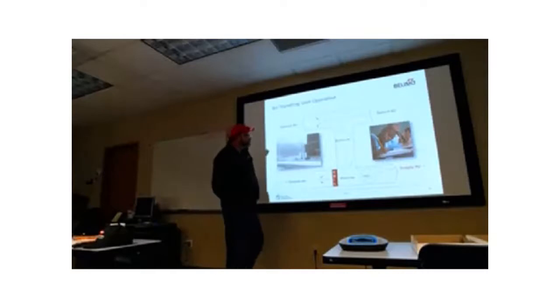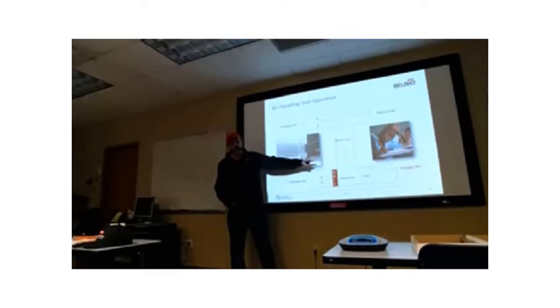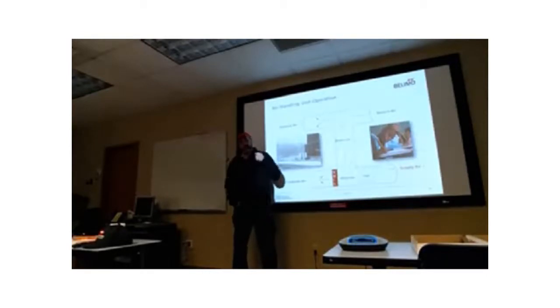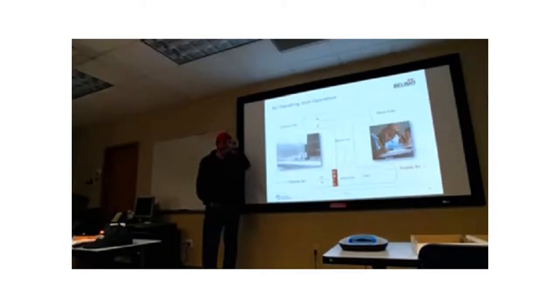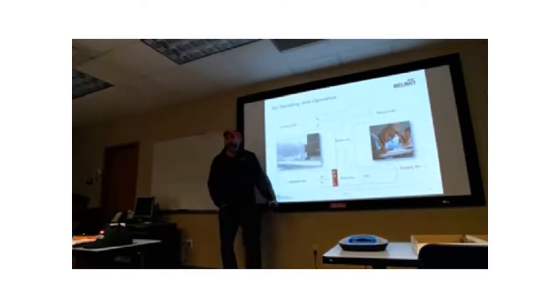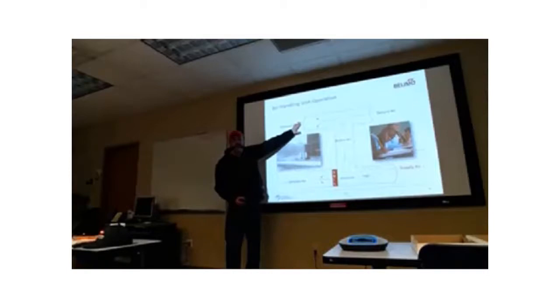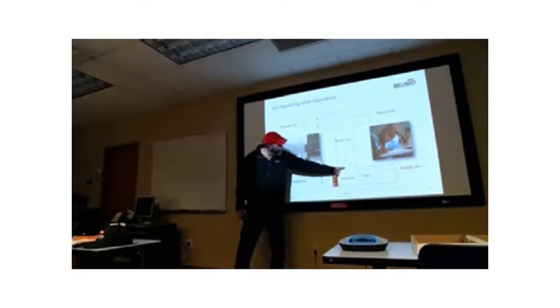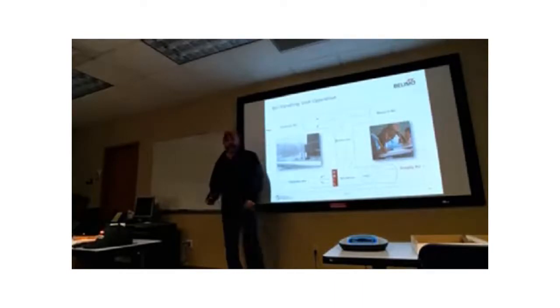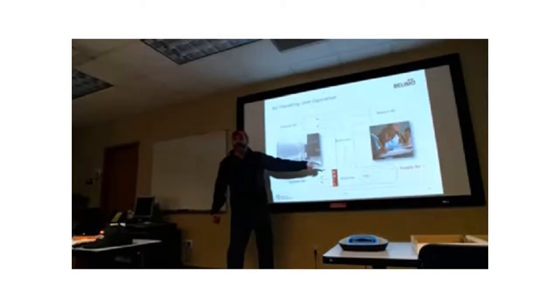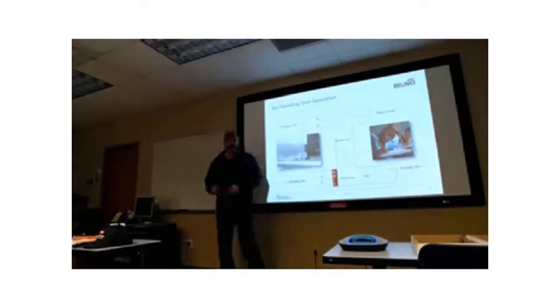Well, if it's going to be fail safe, it would be fail open, right? So I can still recycle air, still heat or cool. Well, that's one possibility, but there's another situation. If the fan comes on and this damper is in some position other than open, like on morning warm-up, we turn on the building, circulate the air, outside air is closed, relief air is closed, we circulate the air and bring up temperature. If that damper fails in some position other than open and that fan starts, what's going to happen? Collapsed ductwork, right? Ugly. That mixed air plenum has a significant negative, and it will collapse it.